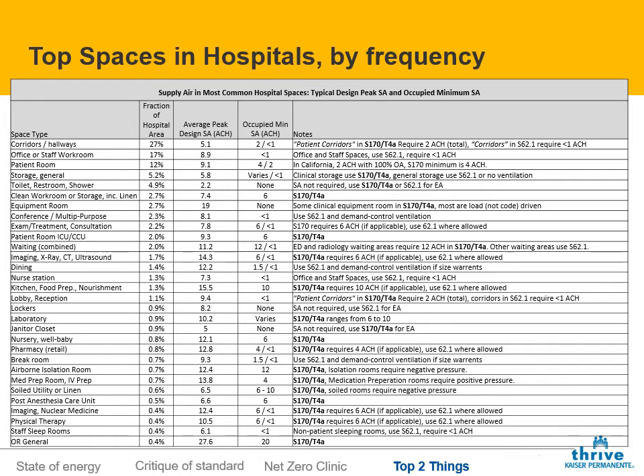Conference rooms, we're seeing our design engineers design these for 8 air changes. That's an opportunity. That's a 90% turn down opportunity, right? Those could be almost completely shut off if you had an occupancy there. Look at the top 3 though. Look at patient rooms. Our average design engineer puts in a peak of 9 air changes in the patient room. For the minimum, California has the advantage. Anytime you're in economizer mode, you can drop to 2 air changes, which is an 80% turn down. But even outside of California, the minimum is 4 air changes, which is a 60%.